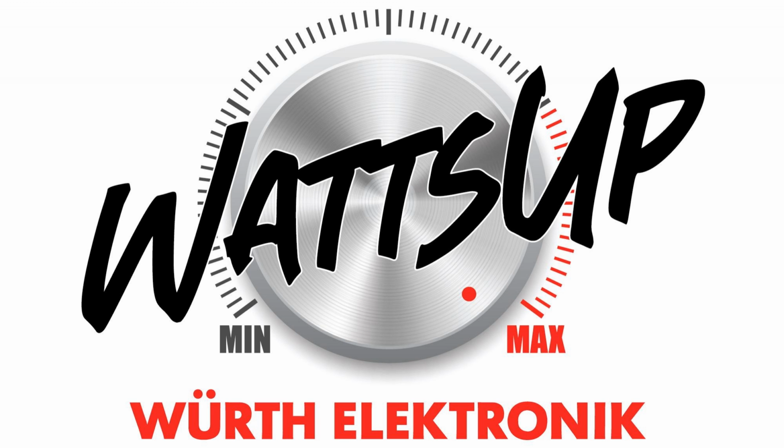So just how do I figure out which current sense transformer to use? Okay, it's a fairly easy process, but there are some calculations. It's a little more than I can get to in a podcast, but I'll say this much: you need to determine the turns ratio, and you calculate the flux density or volt microsecond rating needed, and then you calculate the maximum error due to the magnetizing current.